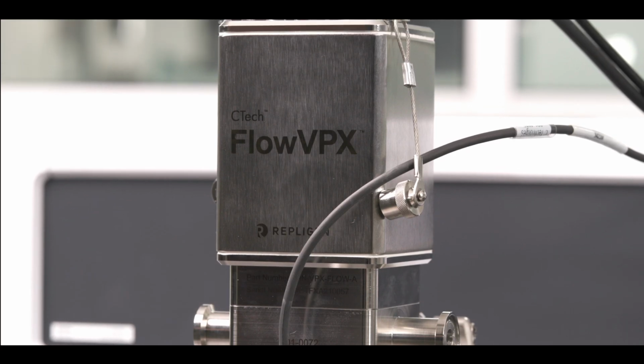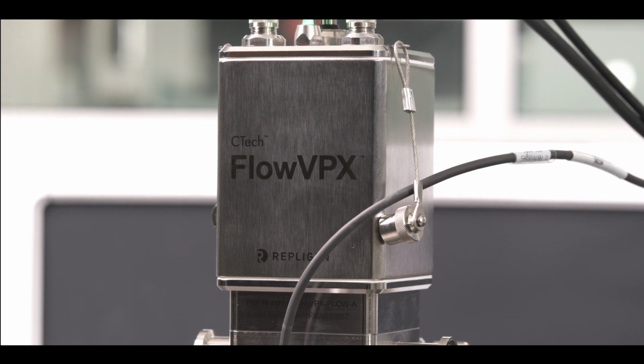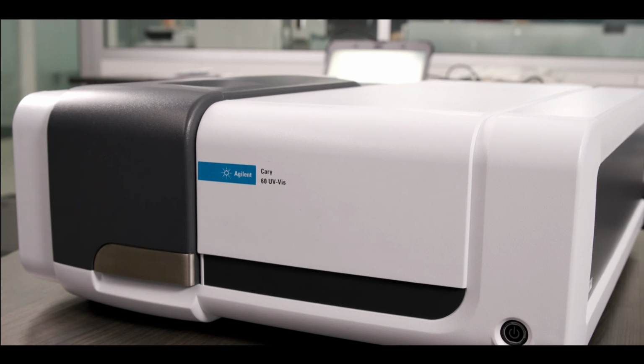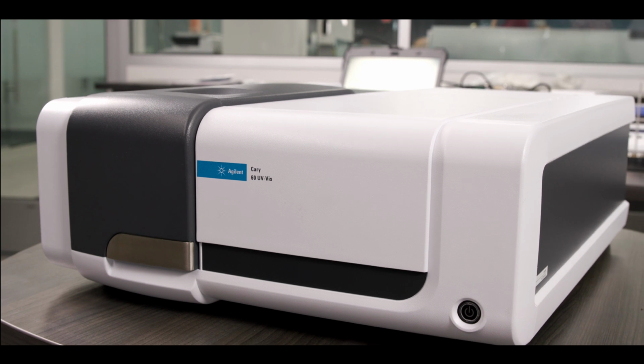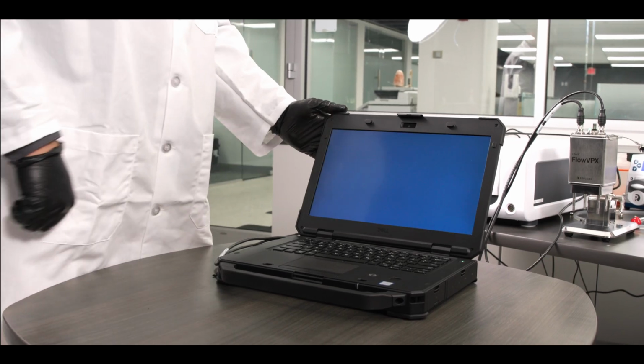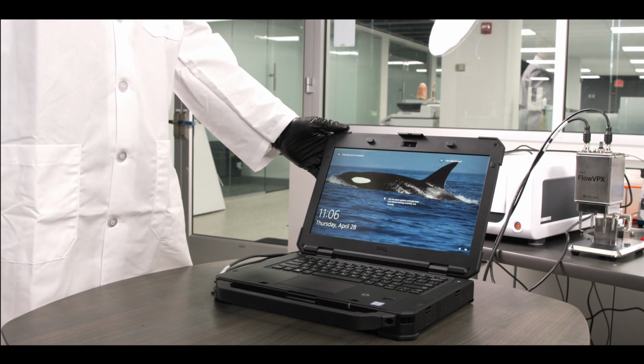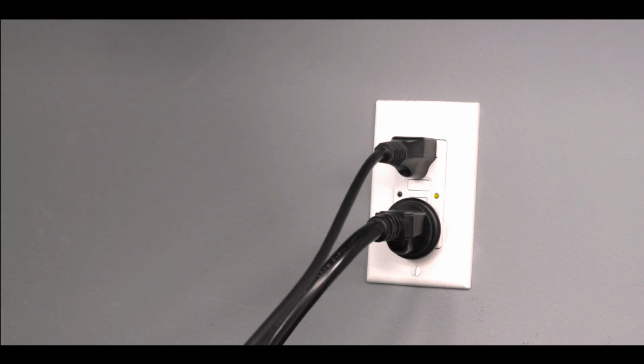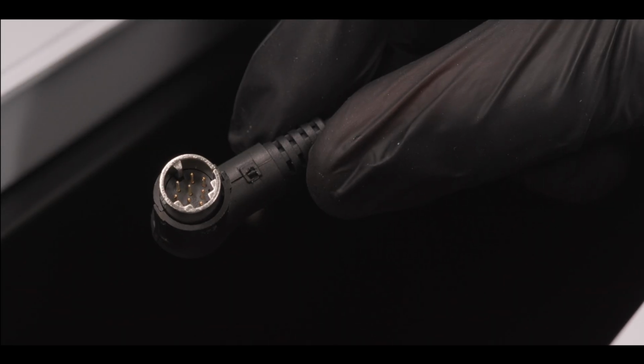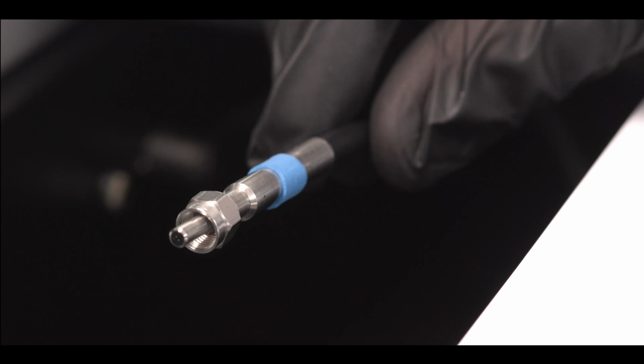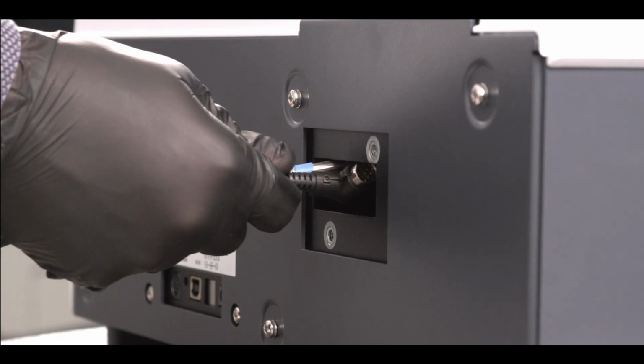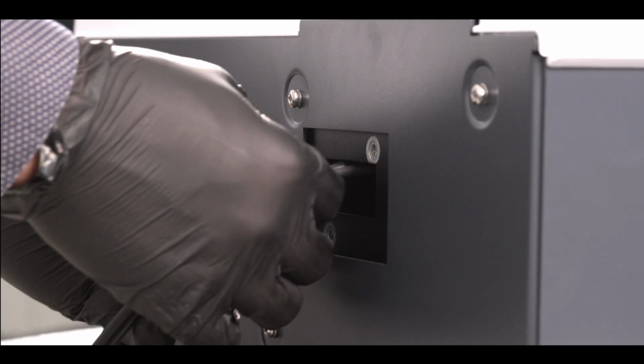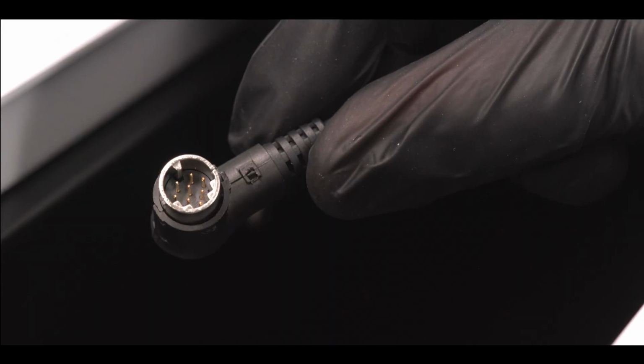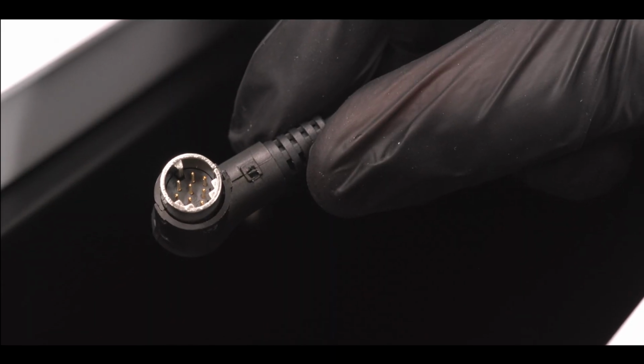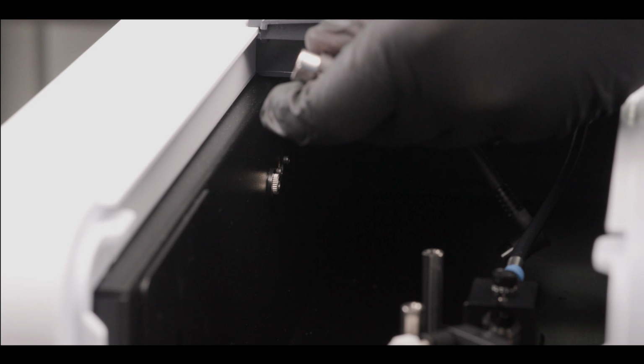Today we'll go over how to install the FlowVPX instrument into your lab bench. The FlowVPX system incorporates a Cary 60 spectrophotometer and a ruggedized computer included with the system and requires access to a power outlet. Pass the detector cable and the SMA hex nut end of the delivery fiber through the open accessory port at the back of the Cary 60 into the sample compartment. Connect the black right angle plug of the detector cable into the wall of the Cary 60 sample compartment.